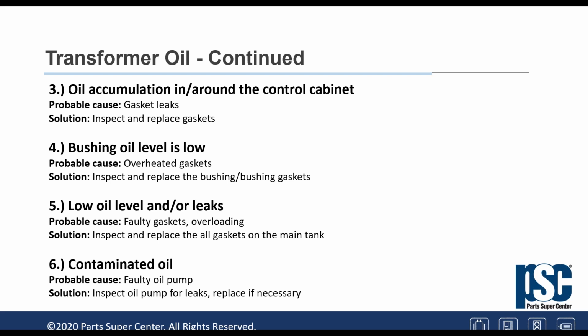Number 5, low oil level and/or leaks. Faulty gaskets, overloading. Again, the overload creates high temperature. The high temperature creates pressure, and pressure has a tendency of pushing oil out of all the mating surfaces.